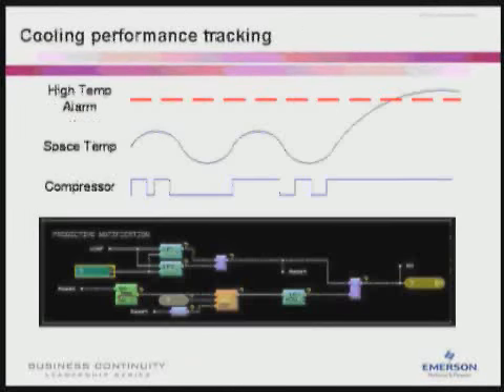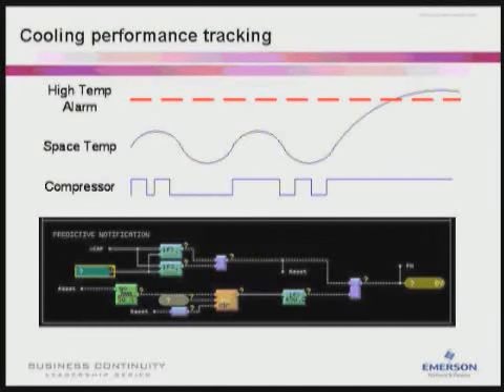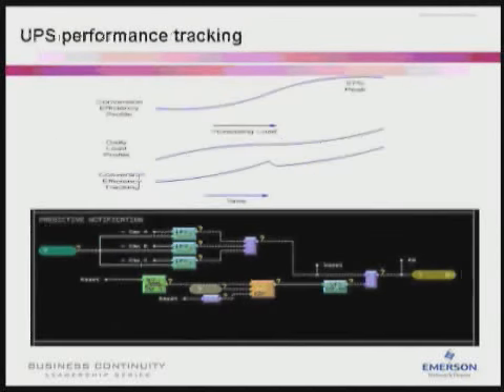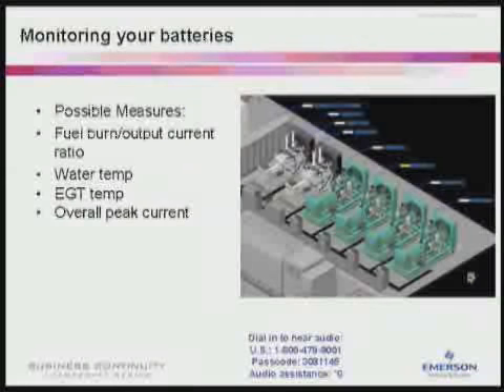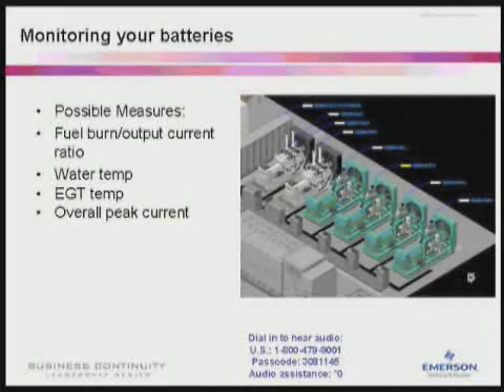Here's an example of cooling telemetry. Rather than just being given an overtemp alarm, you're made aware that conditions are warming, giving you a chance to respond before conditions get critical. Here's an example of UPS telemetry. You could know the power profile of your system prior to any action being taken. This would allow you to identify when out-of-norm conditions occur. For generators, critical temperatures and peak currents delivered may be of most value to you.